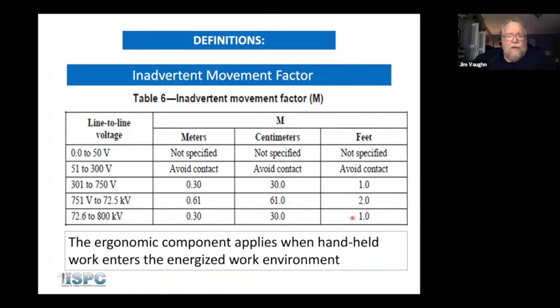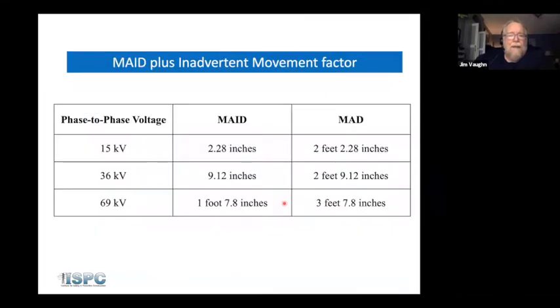And usually people say, well, higher voltage, why is it a smaller distance? Well, the reason it's a smaller distance is because we have the benefit of spacing of conductors and airspace across insulators that make our inadvertent movement less of a hazard as compared to distribution, where we'll be up between the phases and up around the cross arm, and everything is already only 12, 14, 18 inches apart. So that's the reason why we add that distance in MAD.